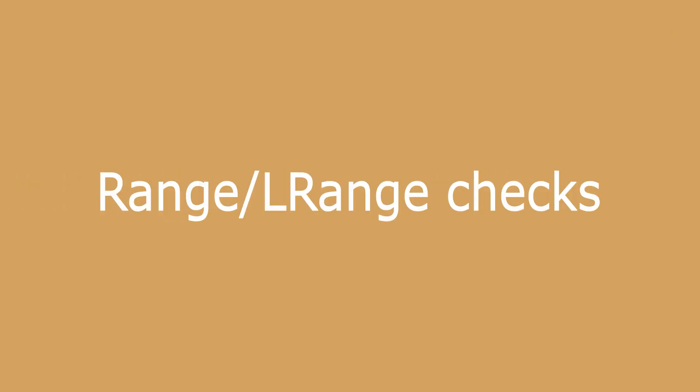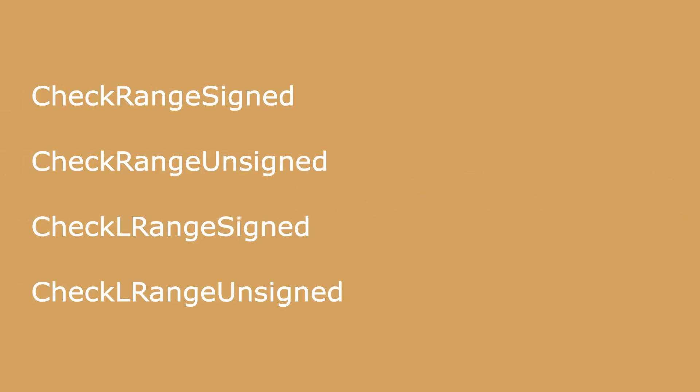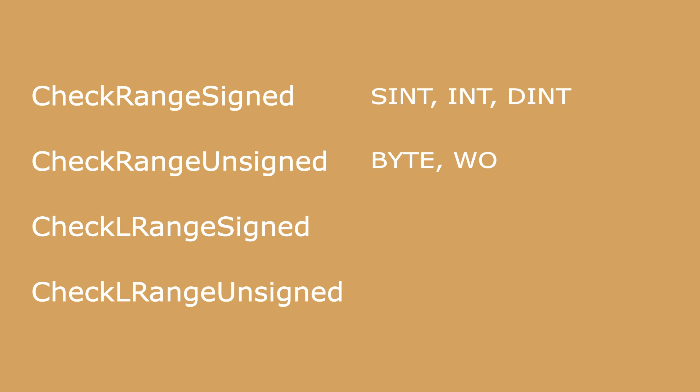Now we want to talk shortly about the range and L range checks. These are functions which are monitoring the bounds of subrange data types. They are called check range signed or unsigned and check L range signed or unsigned. Check range signed checks subrange types of the type SINT, INT, and DINT. Check range unsigned checks subrange types of the type BYTE, WORD, DWORD, USINT, UINT, and UDINT.